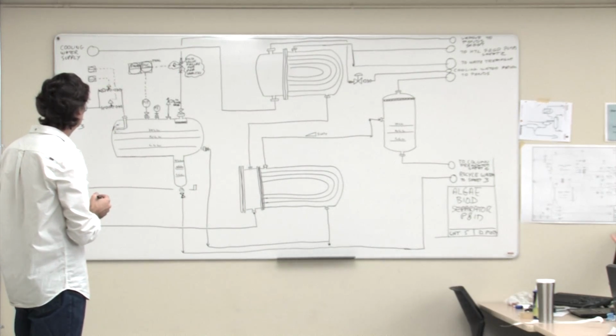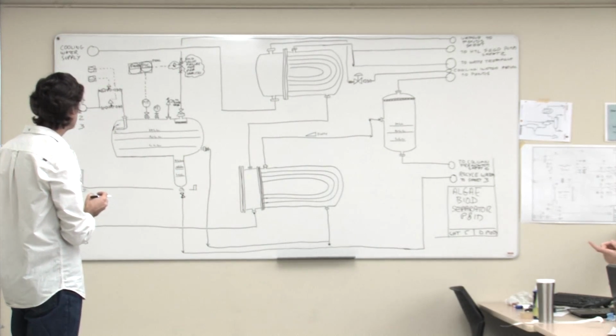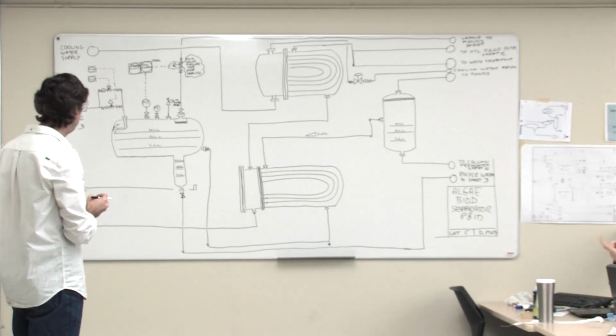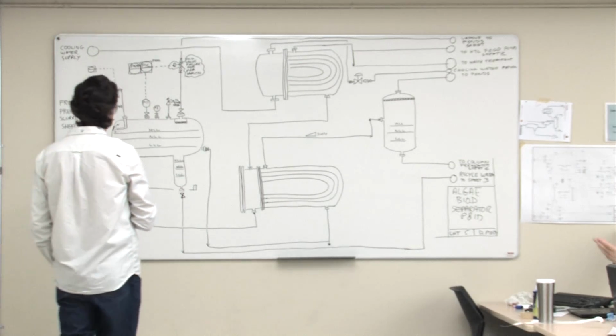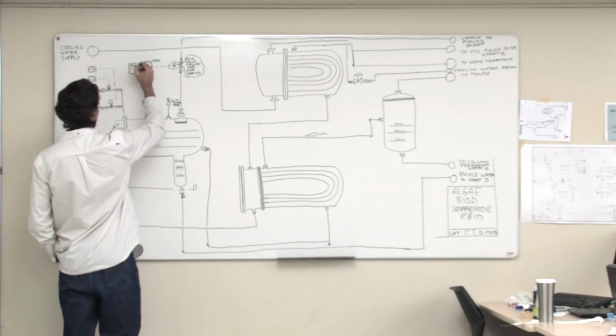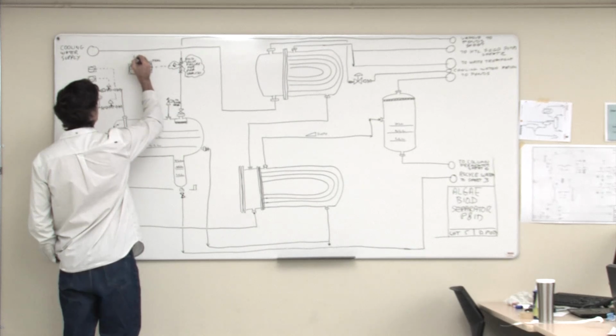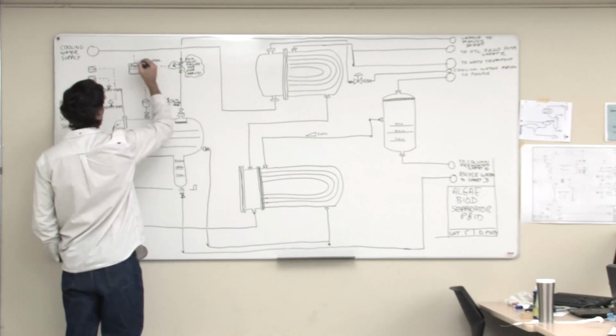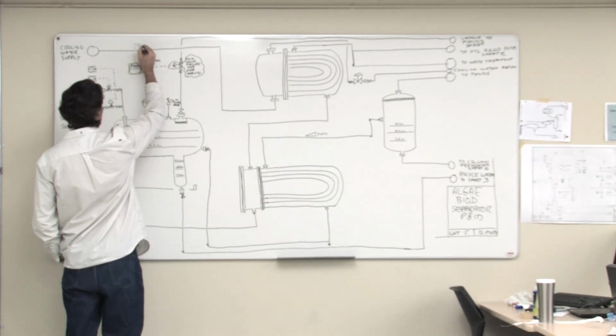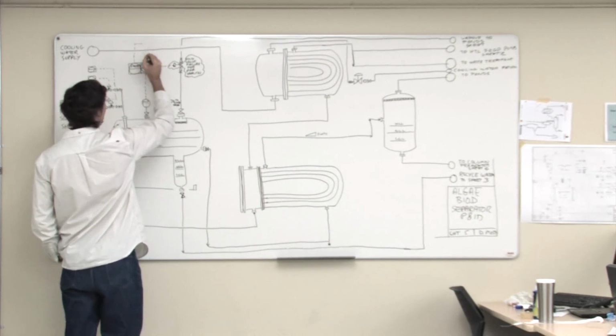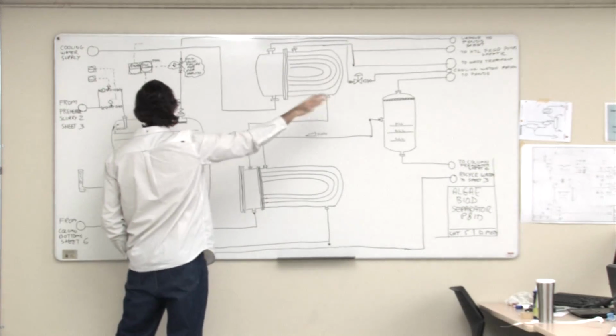If you were to send a signal off, say, to the feed pump, which is on a different sheet - do you bubble that like these, or how do you indicate it goes to a different sheet? You'd have to show it up, and you'd probably want to rip it right across the P&ID. Sometimes you'll cheat and just show it right here, but it's not good practice - it's better to pull it right across the sheet.